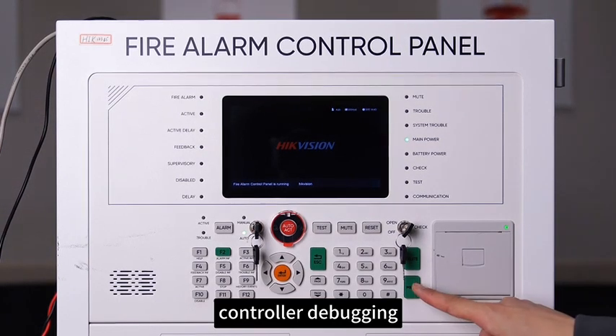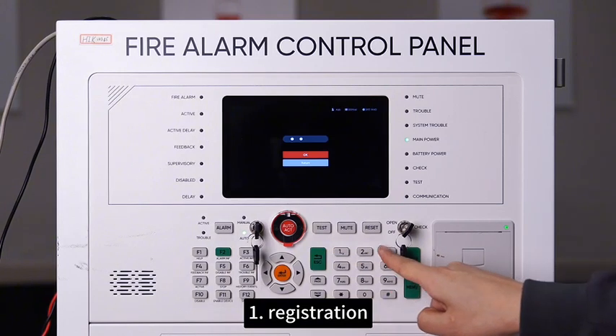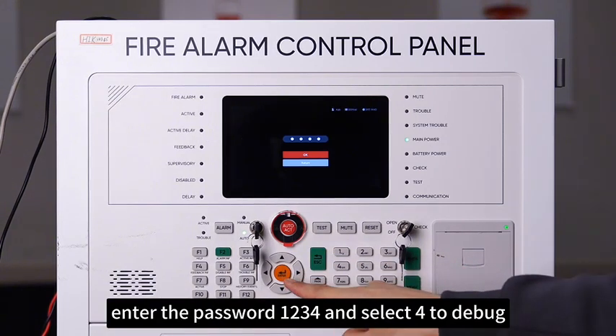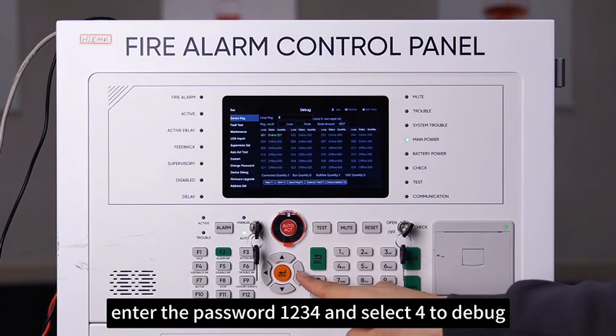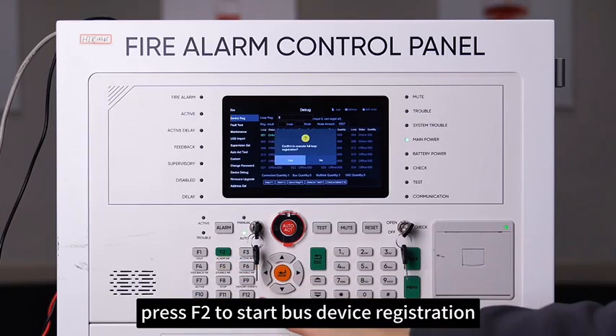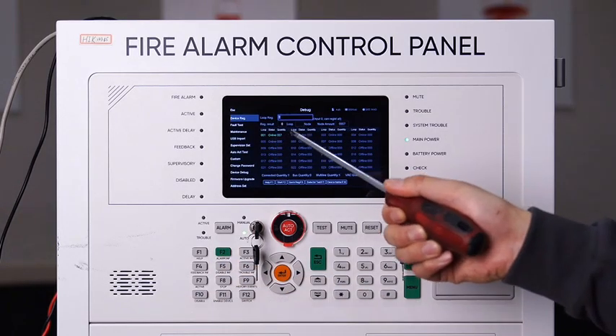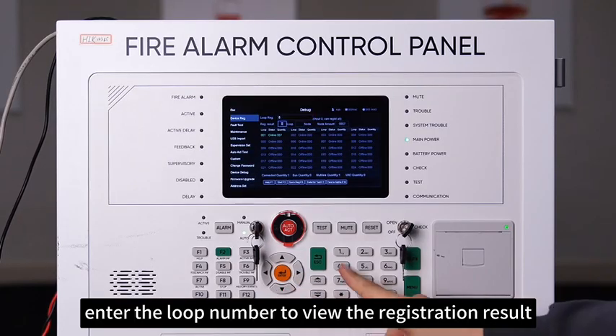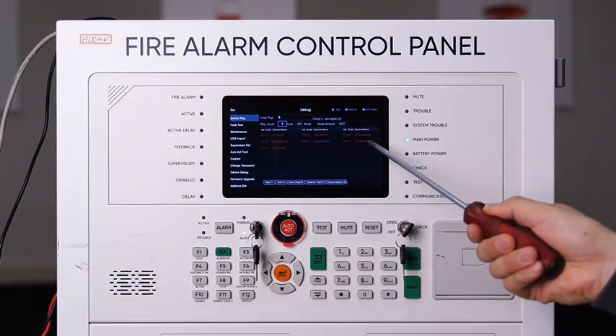Controller debugging. First, registration, press the menu key, enter the password 1234. And select 4 to debug. Press F2 to start bus device registration. After registration, enter the loop number to view the registration result.